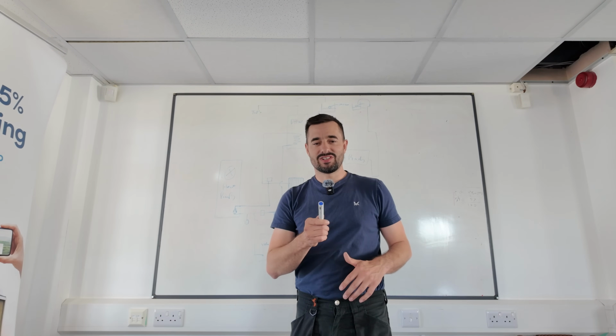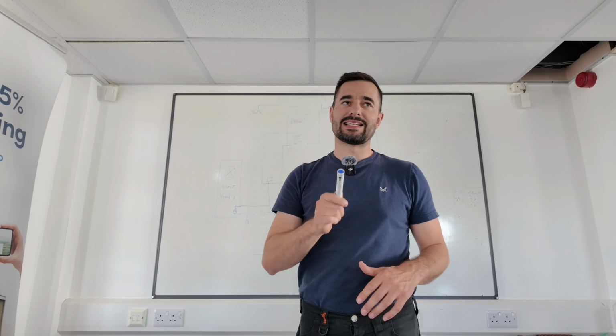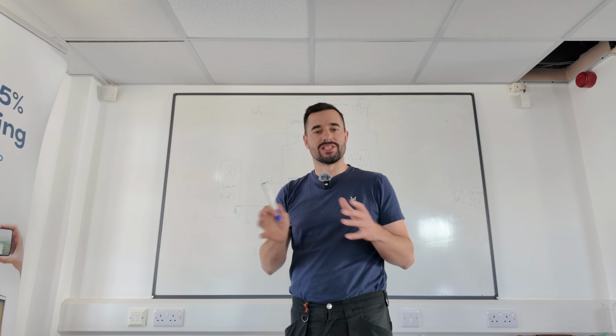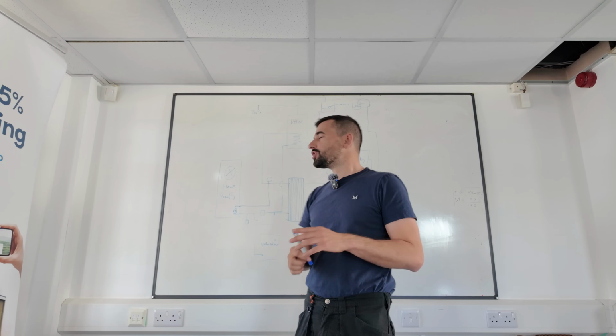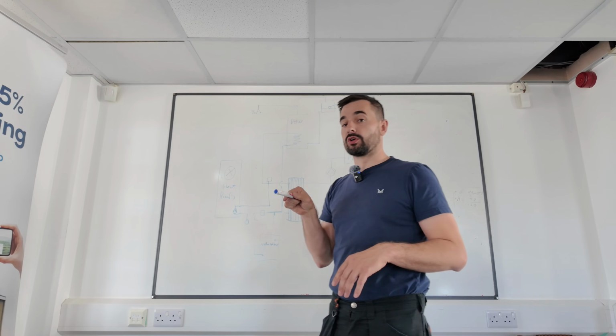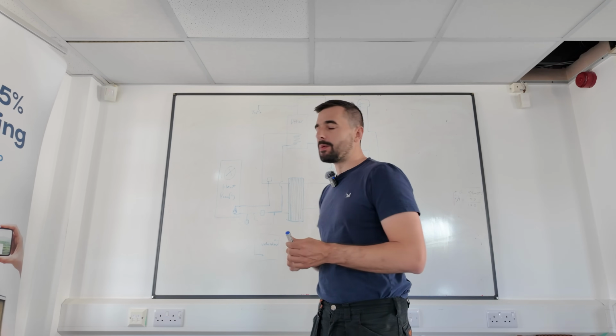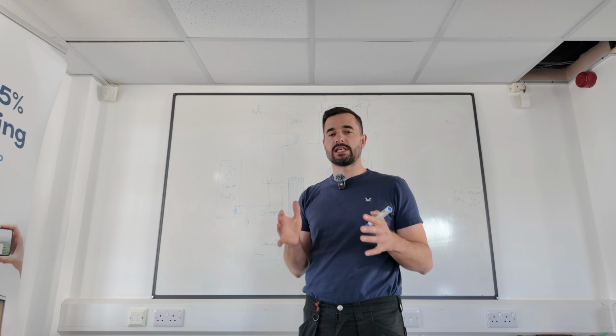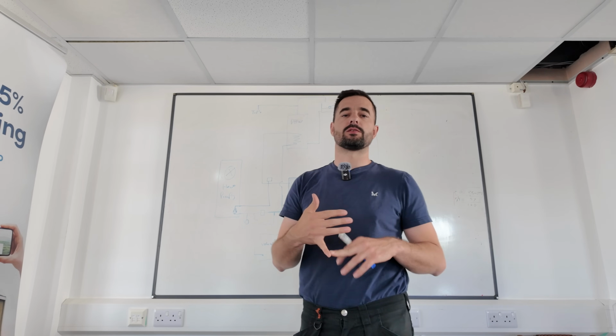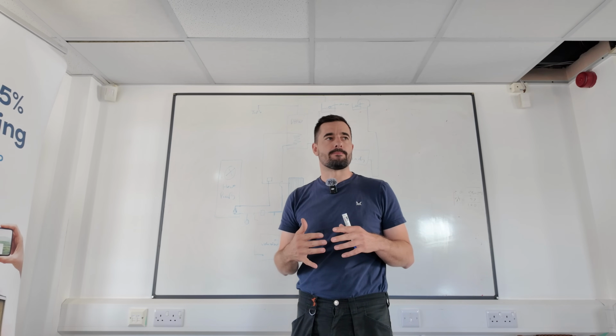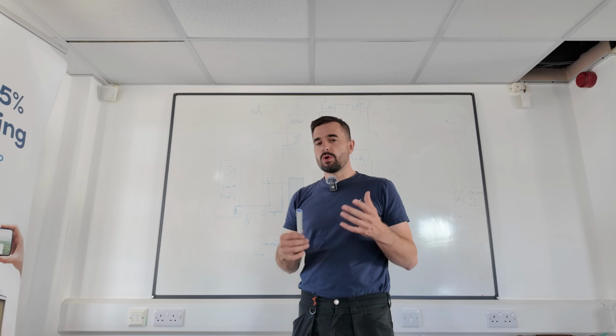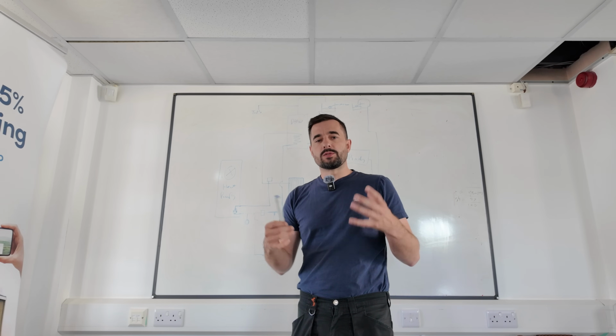I was just editing the video and I thought I hadn't been quite clear enough about the layout of pipe and the reason why we'd done what we'd done. So I've drawn it out on this board and I'll talk you through it. Basically, most modern heat pumps need to work on a pressurized system, so they'll need a minimum pressure to actually function. So you'll typically always pressurize a system.